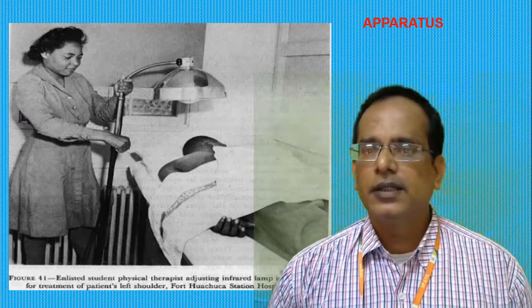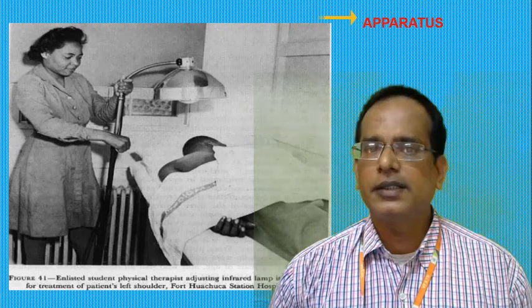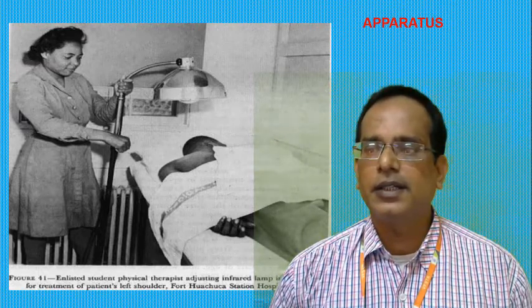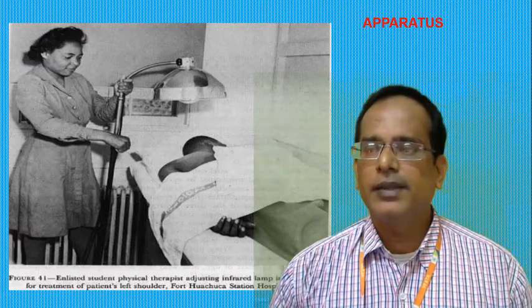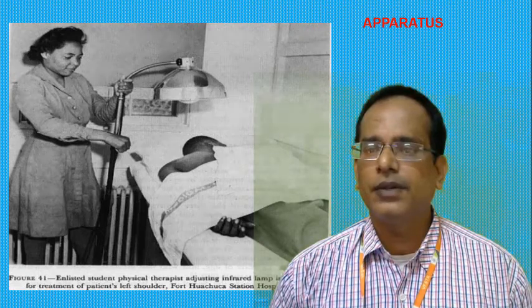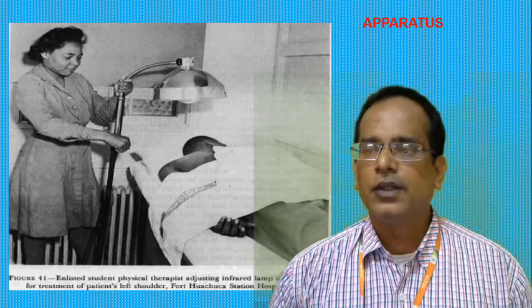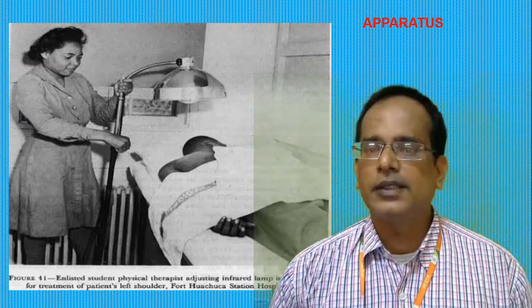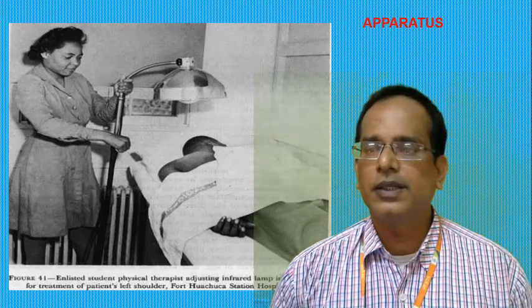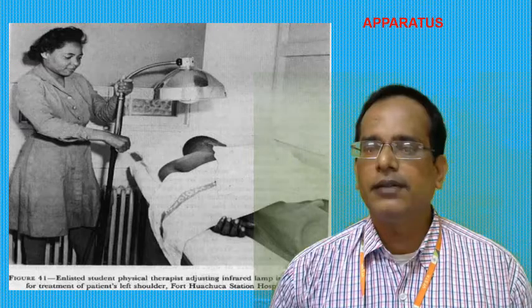Here the device may be a luminous or a non-luminous generator. It will take some time to heat up. It won't give heating immediately. So it should be switched on 5 to 10 minutes before treatment. A luminous generator needs no warm up time, and it can be switched on once the person is ready for the treatment.